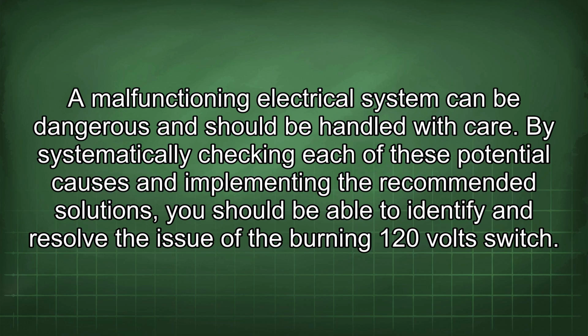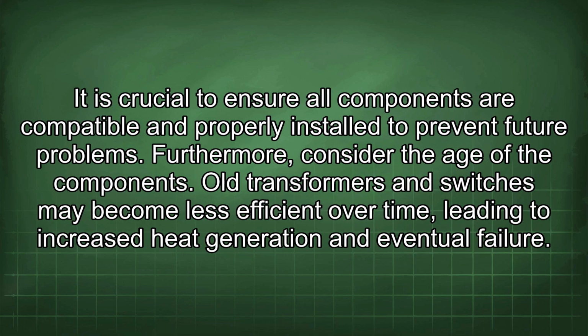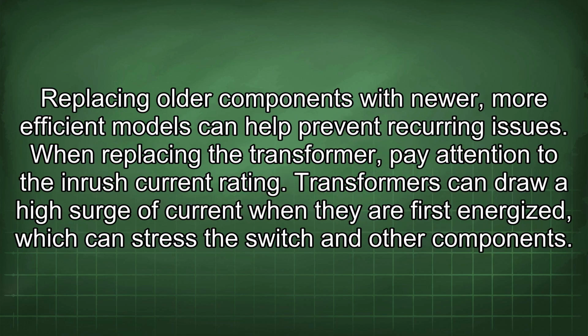By systematically checking each of these potential causes and implementing the recommended solutions, you should be able to identify and resolve the issue of the burning 120-volt switch. It is crucial to ensure all components are compatible and properly installed to prevent future problems. Furthermore, consider the age of the components. Old transformers and switches may become less efficient over time, leading to increased heat generation and eventual failure. Replacing older components with newer, more efficient models can help prevent recurring issues.